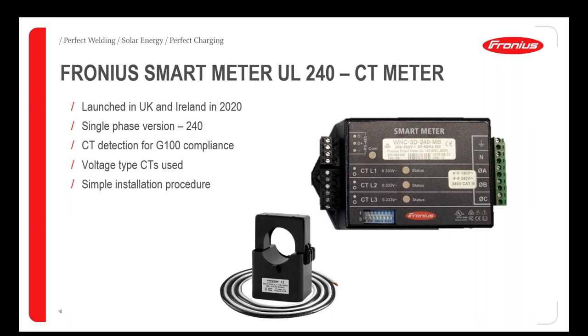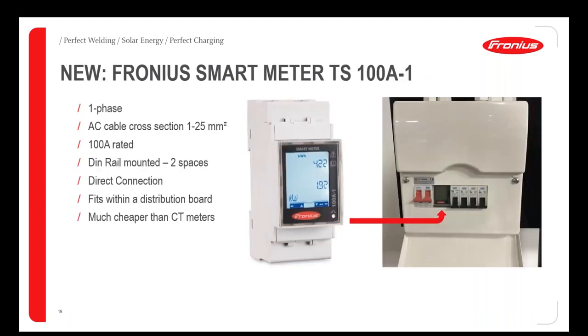You do have to manage that CT and get it secure around the cables. So there is potential for getting the CT back to front, having it loose, or maybe making a mistake with the wiring. The advantage of the new TS100 meter is that it is a direct connect meter. It doesn't need a CT, and it fits nice and neatly within a distribution board. It's a DIN rail mounted device, and it takes up just 2 DIN rail slots. As you see next to these MCBs, it fits securely within the enclosure. Without a CT, we simply connect in from the main switch into the smart meter and then out to the loads. It's a very simple solution, as long as you have the space within your enclosure.